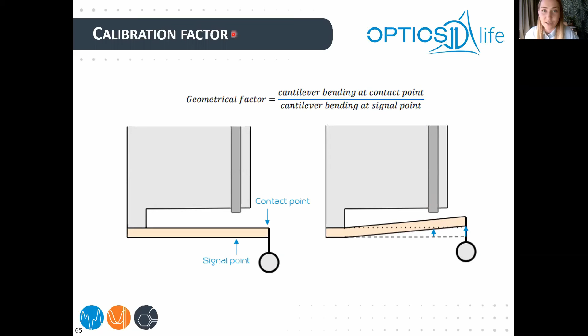So during calibration, we do it on something very stiff, because then we know that how much the piezo moved is the real distance, and whatever the fiber sees is that smaller distance, due to the refractive index of the medium and due to the mismatch actually. So based on that, we can calculate this geometrical factor.